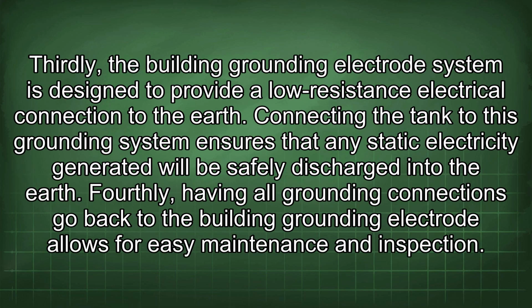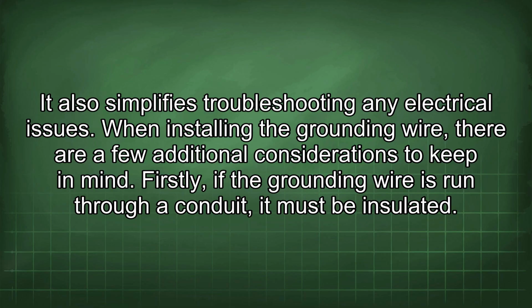Thirdly, the building grounding electrode system is designed to provide a low-resistance electrical connection to the earth. Connecting the tank to this grounding system ensures that any static electricity generated will be safely discharged into the earth. Fourthly, having all grounding connections go back to the building grounding electrode allows for easy maintenance and inspection. It also simplifies troubleshooting any electrical issues.